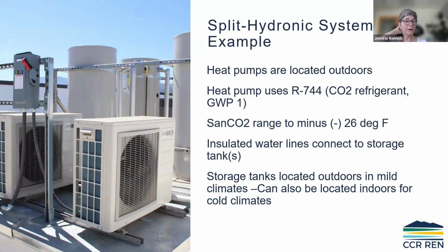And then the split hydronic system, this example here is from a really mild climate. So even though we've got the outdoor condensers outside, the climate zone is mild enough that we can have our first level of storage tank also outside. And then we've got swing tanks, bigger tanks inside. But these Sanden or SanCO2 units, they can go down to minus 26°F.